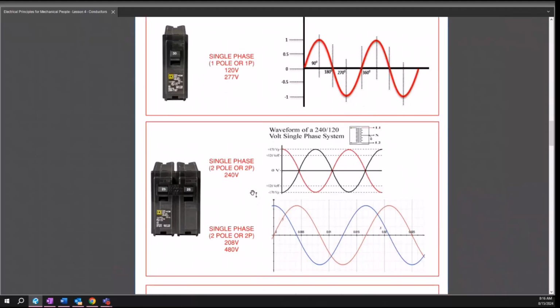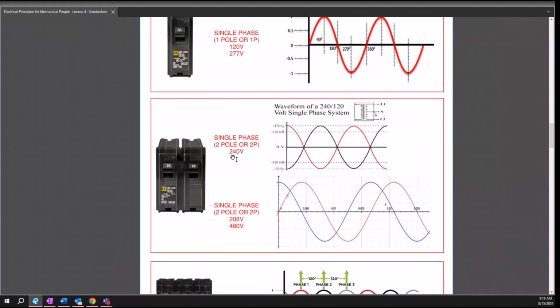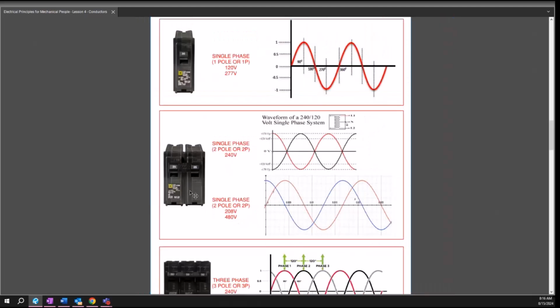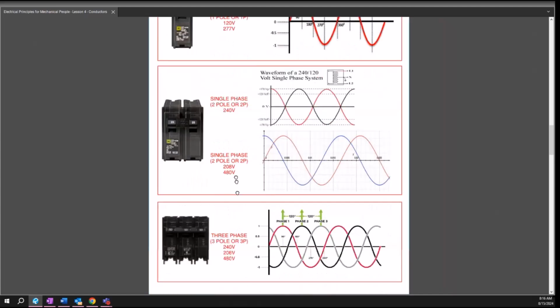Now here's the confusing part: when you get two poles, it is still technically single phase. That's why you have to specify, hey, I've got a 240 single phase fan, or a 480 single phase HVAC unit, something to that effect. When you're in the 208, 240, or 480 voltage range but still only have two poles, that's still single phase. There's no such thing as two phase, as it were. It's either single phase or three phase.